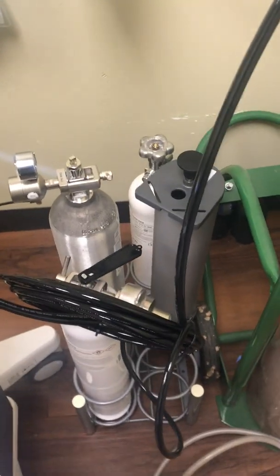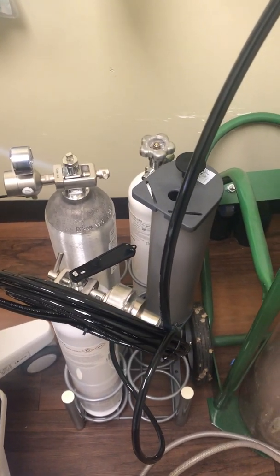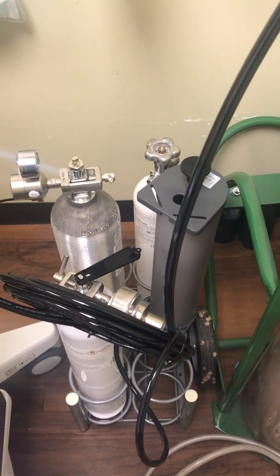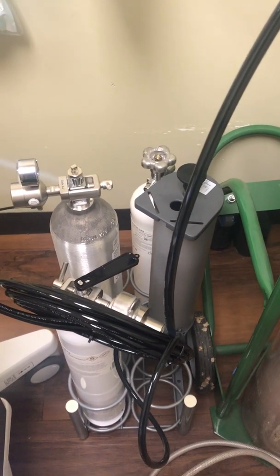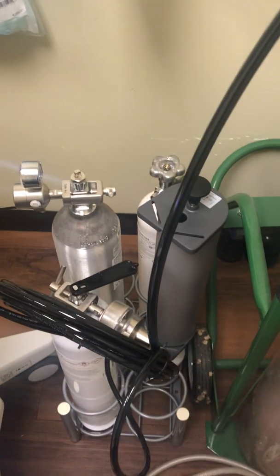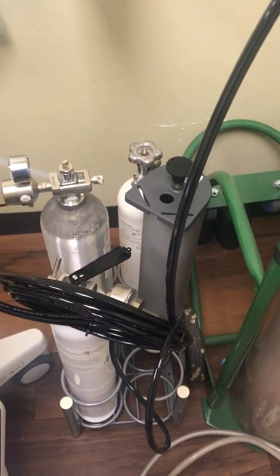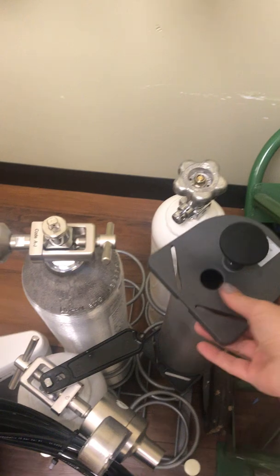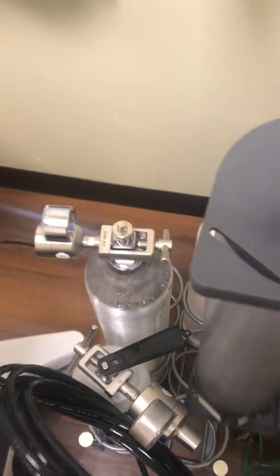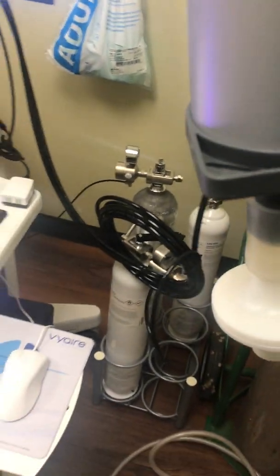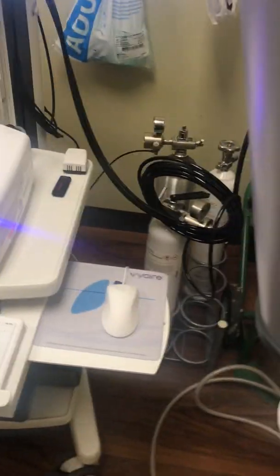Okay, so then we've got the syringe over here. Also, I wanted to note too with the CO2 tanks, they're not the same, they're not compatible, so we won't be able to use the old ones that we had for the VMAX, and that's something to keep in mind. So this has got one of the filters on it. Again, we cannot use the filters that came with the VMAX. Not compatible, so they won't fit.